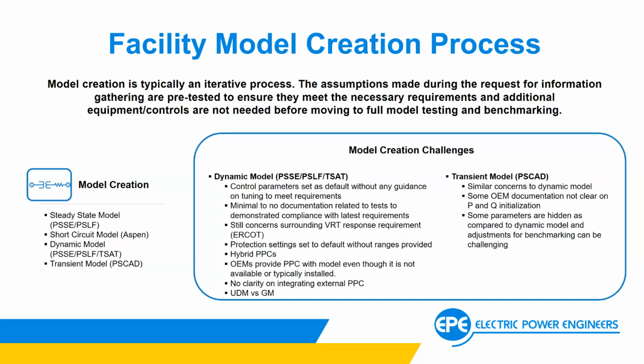Also, some parameters are hidden within these models. Some of them are totally black box. So any changes that I make, say in the PSS/E space to a user defined model, I can't make in PSCAD without either the OEM doing it on their end or providing an updated model with those parameters. And in some cases, the parameter names between the models in PSS/E and PSCAD may not even be the same, so it takes a little bit of fishing and understanding of the models to cross correlate those between the two spaces.